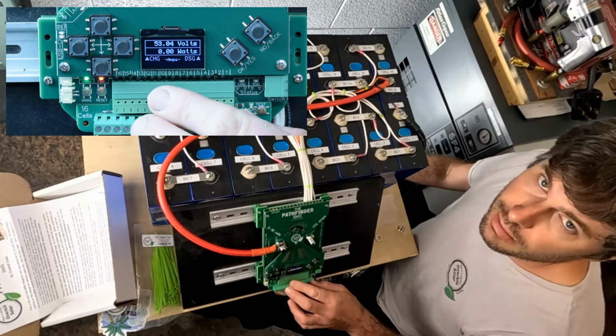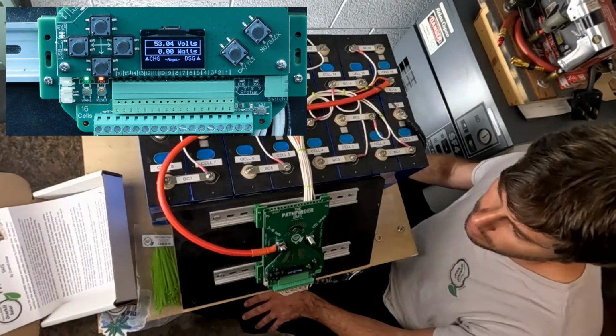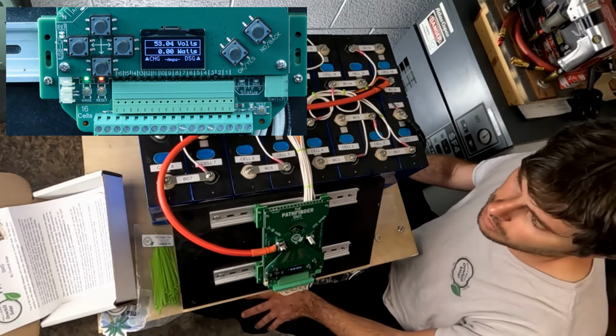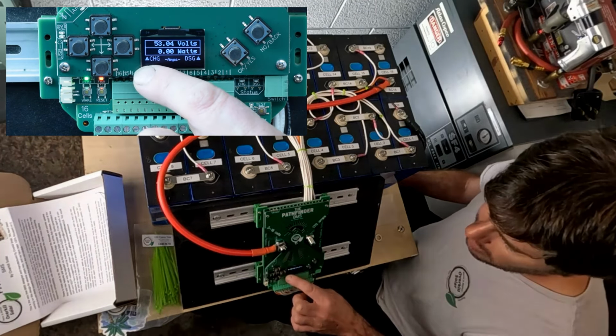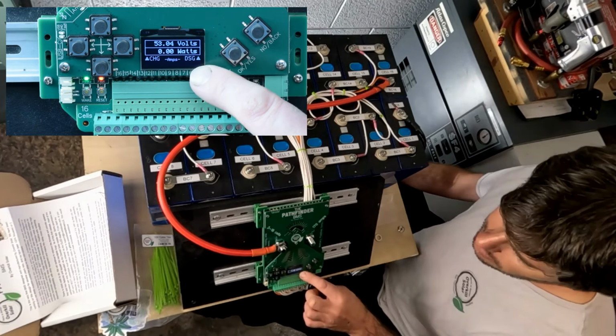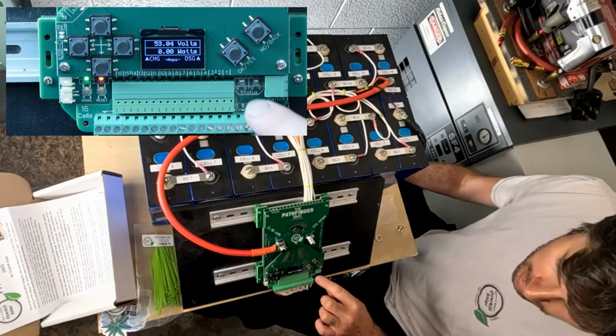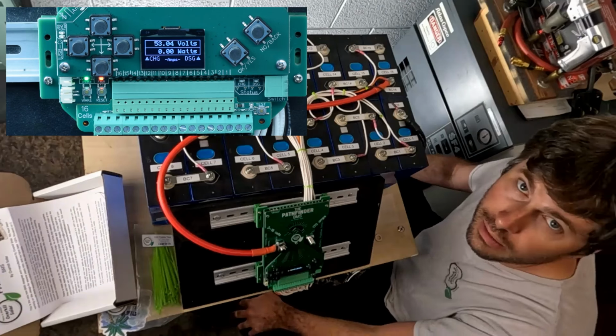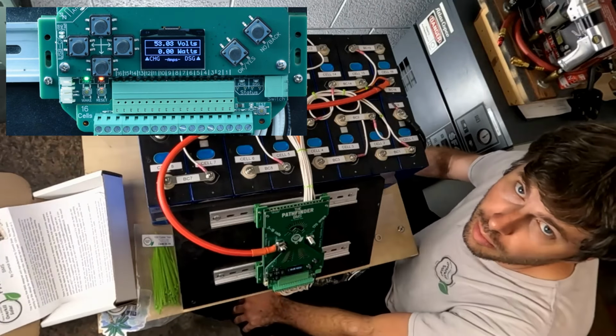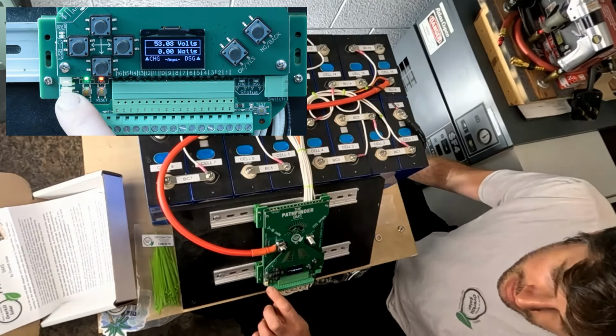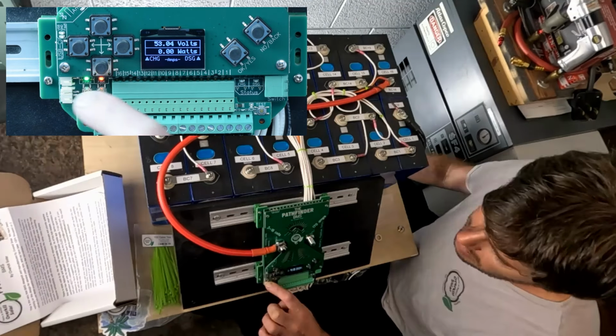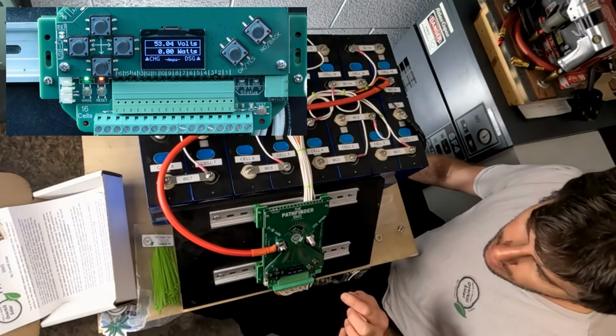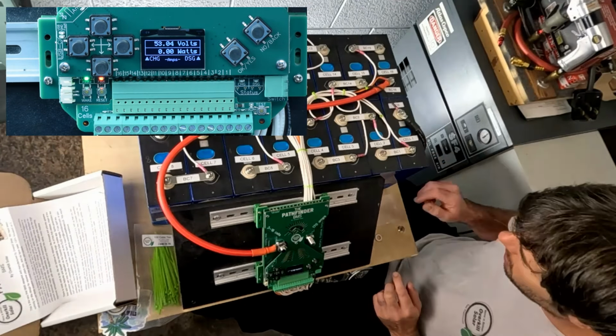If you do see some current here, in a later video I'll go over how to calibrate the null current. What we see here is two warning triangles next to charge and discharge, with no green lights. That means charge and discharge are both switched off, because I haven't plugged in the temperature sensors yet. So this is actually shut off because of a low temperature alarm.